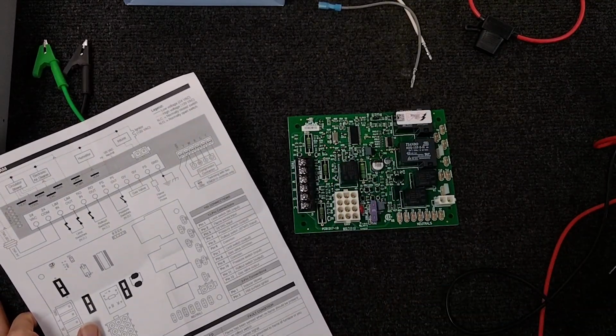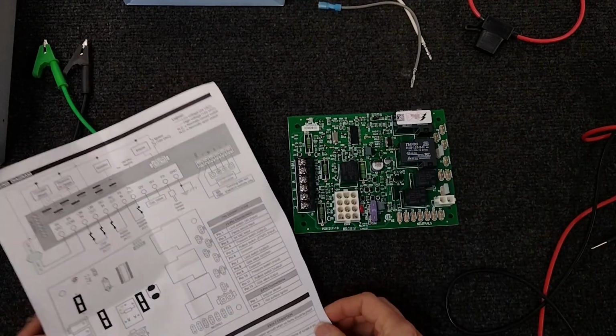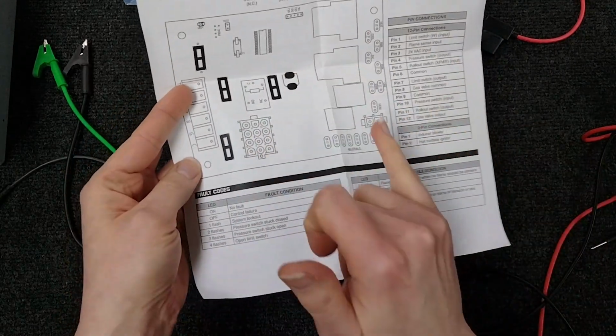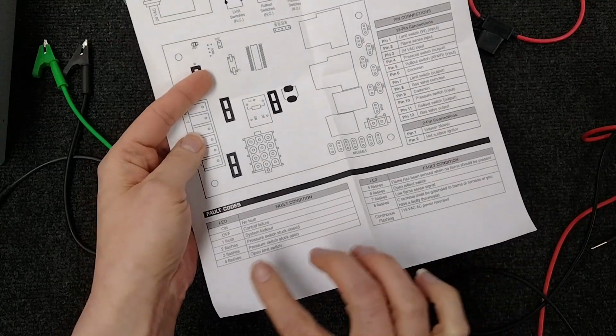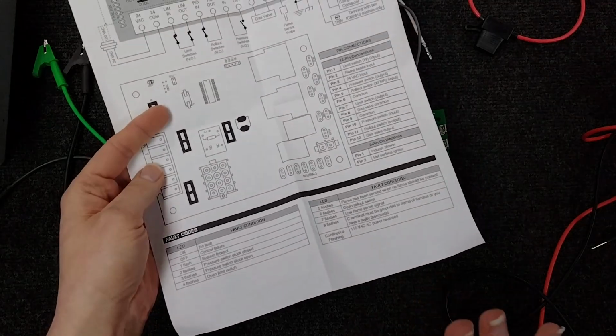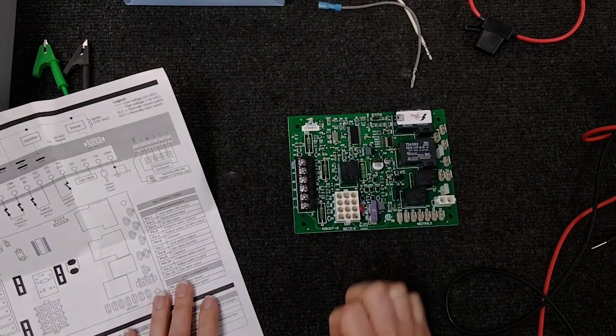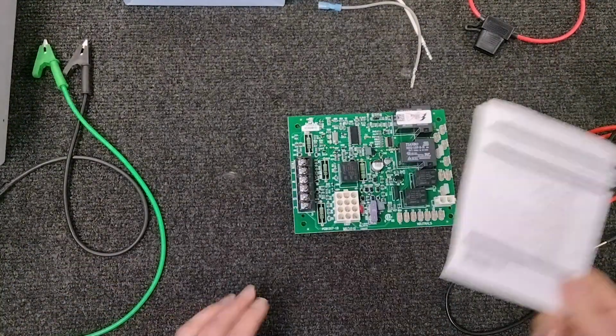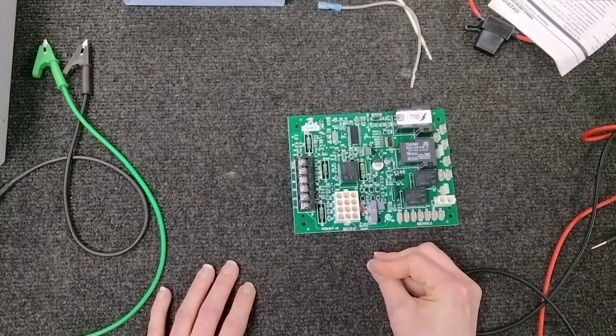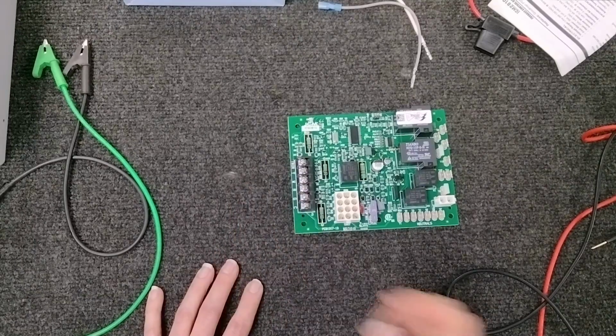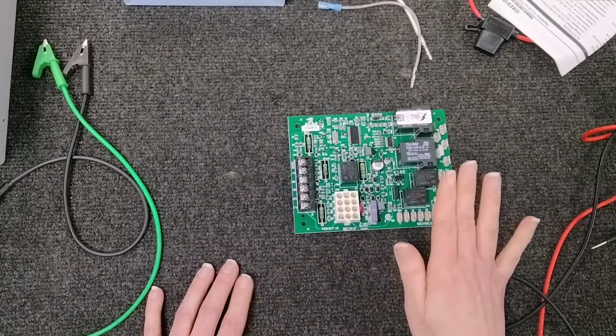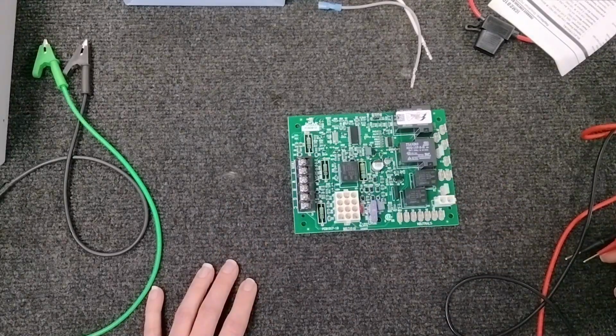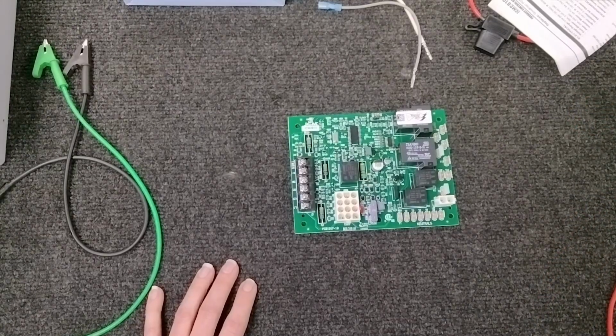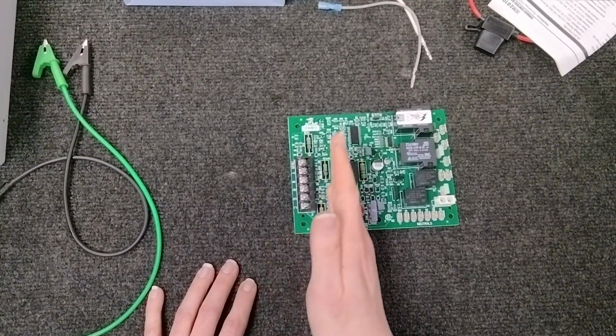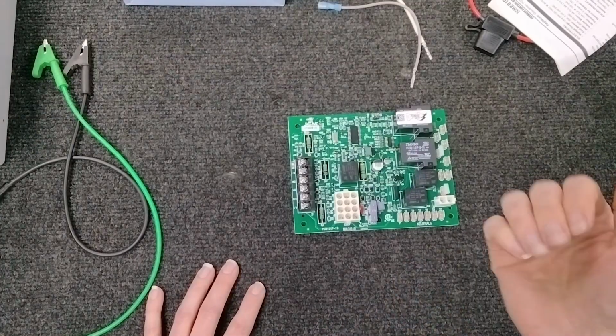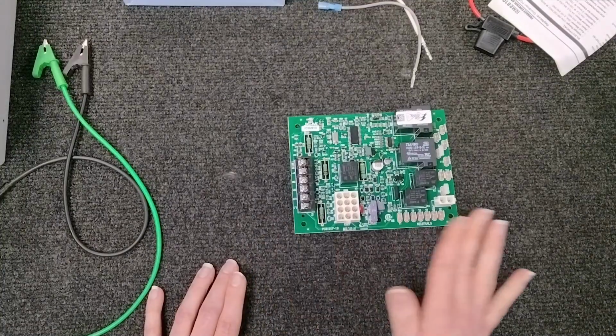But when your heating fails, it should blink a fault code. These are generally below your wiring diagrams, as we've shown in other videos, and it will tell you what's going on. Now, if that light does not come on, the board is not getting power or it is bad. But going back to what we were talking about earlier, just make sure you do have your 120 or 240 going into the unit. Make sure it's not something like a power surge that happened that took out your high side power. If you have gas heating, your door switch, possibly, as we spoke about, a breaker, just kind of tick all those boxes off so you're not having to get more and more frustrated because you've replaced parts and none of it is working.